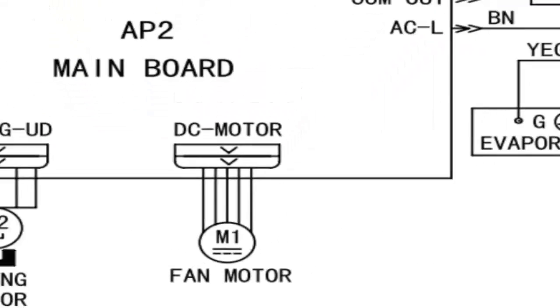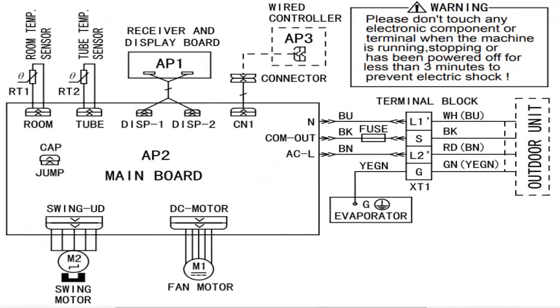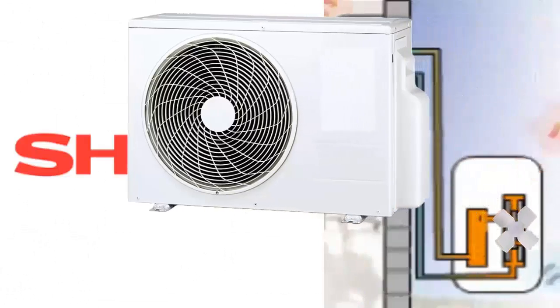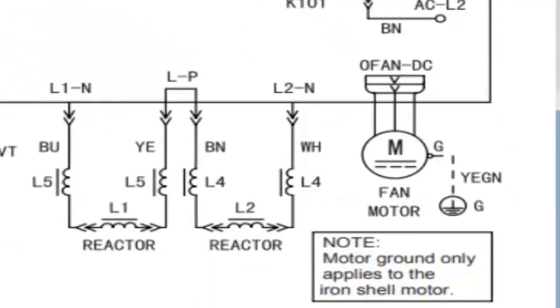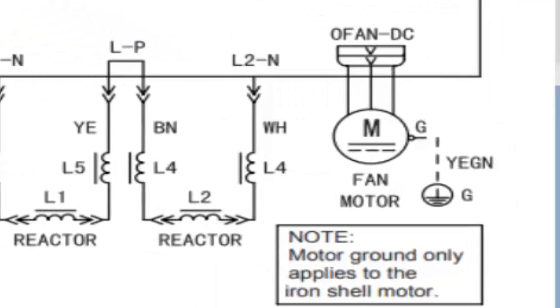However, when the problem is located in the outdoor unit fan, and it is of the BLDC type, the code L3 is generated. This type of fan is powered directly from the external electronic module through 3 wires.